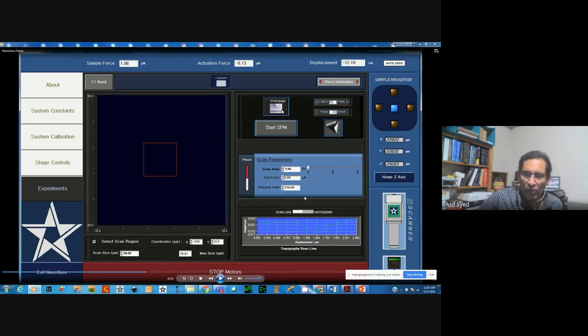But to maintain that set point, you need a feedback loop. That feedback loop has an integral gain. That is the parameter over here. So you put in the right integral gain, and then all these parameters are done. Then you can go and start SPM imaging.